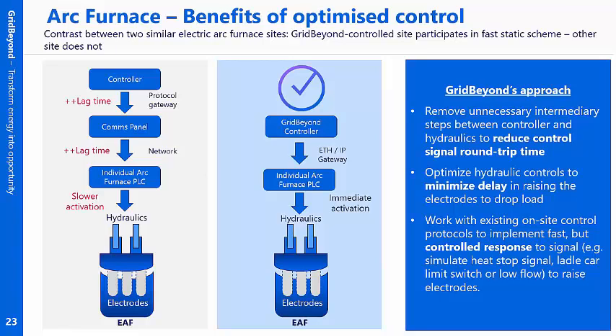The way we have delivered these arc furnaces is by simulating a controlled stop. So if you can imagine a heat stop signal, or a ladle car limit switch, or a low flow, we integrate our signal to simulate one of these stop signals. This raises the electrodes immediately and drops the load immediately. Then the VCB trips. But from our monitoring, we see that load shed in less than a second.